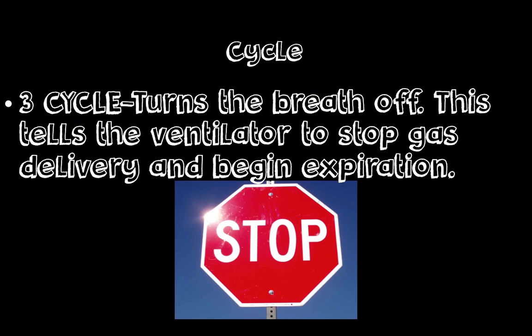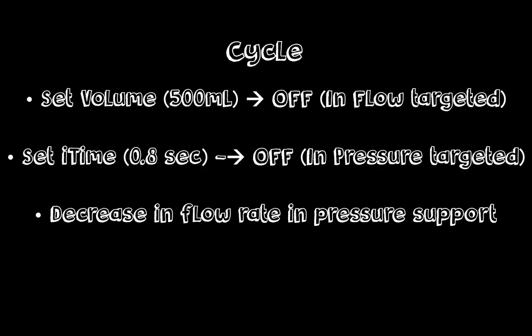Our final phase variable is the cycle. The cycle is what governs the breath to be turned off — it tells the ventilator to stop gas delivery and begin expiration. In the cycle, we have three distinct cycling methods: set volume, set inspiratory time, and decrease in flow rate. If you were in flow-targeted mode, whenever the ventilator reaches a set volume of 500 ml, it signals to stop gas delivery and begin exhalation. If you were in pressure-targeted mode, whenever the ventilator reaches a set inspiratory time of 0.8 seconds, it will stop gas delivery and begin exhalation. If you were in pressure support mode, whenever the ventilator senses a decrease in flow rate in the circuit, it will stop gas delivery and begin exhalation.